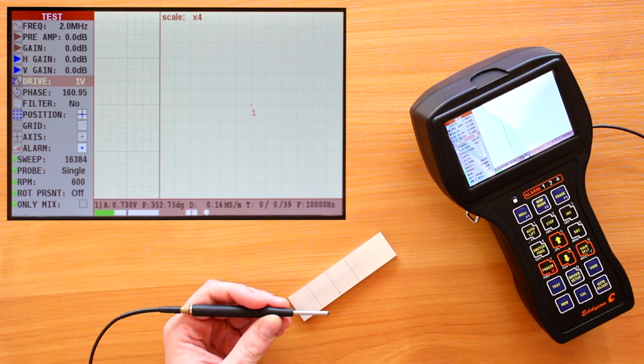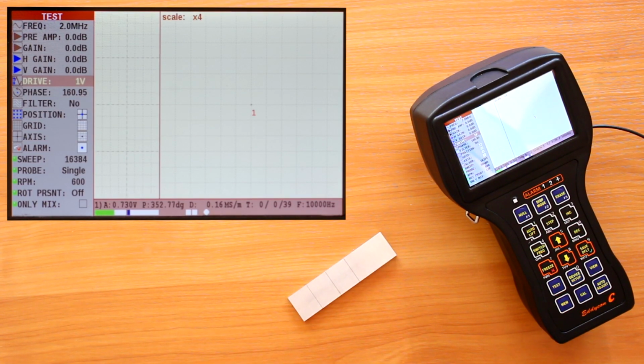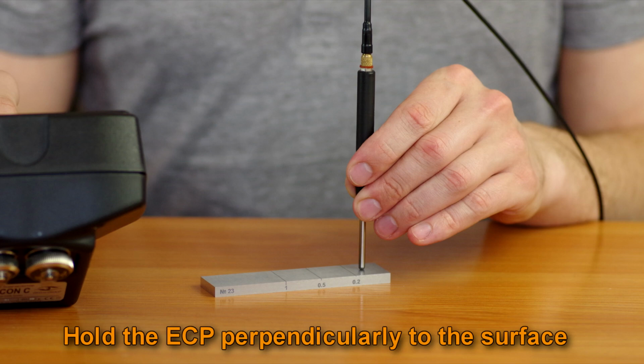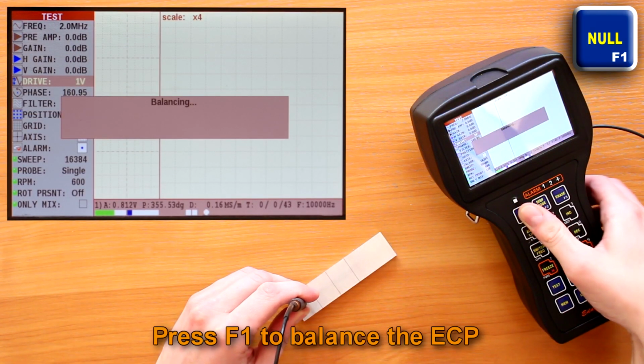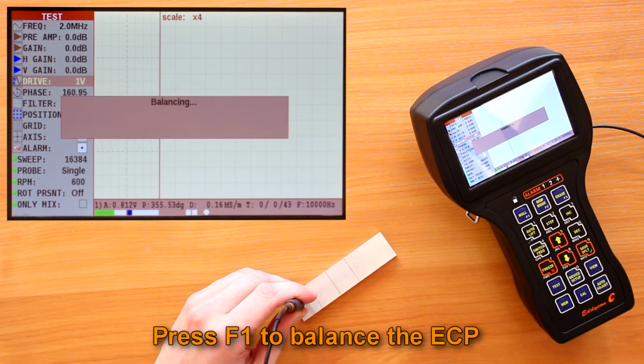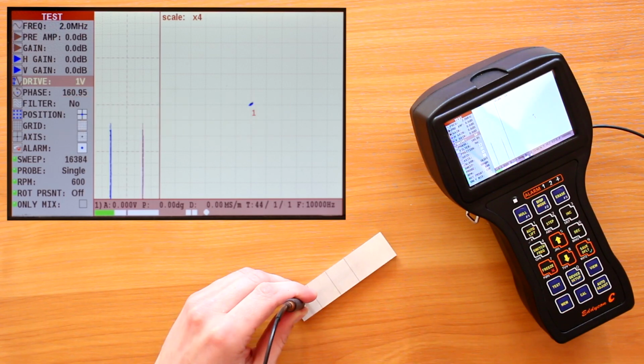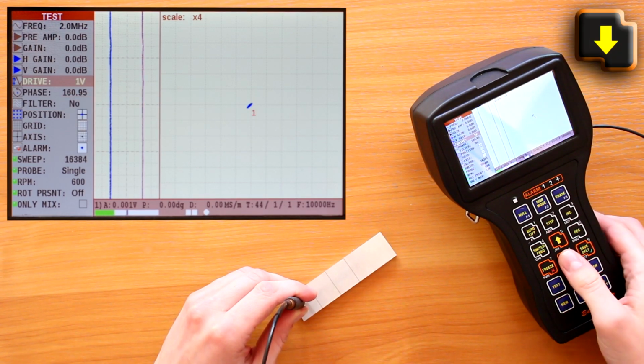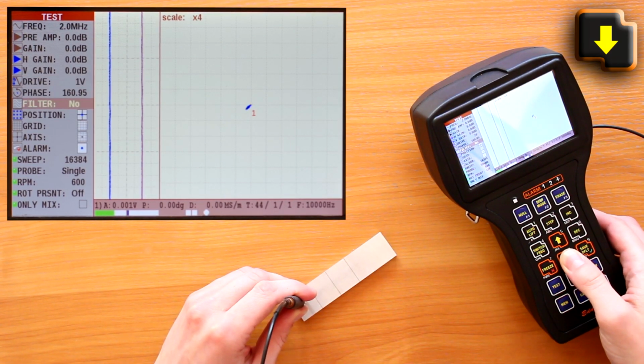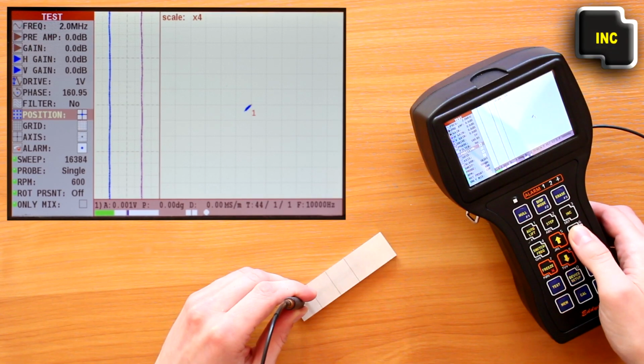Move the ECP to the flaw-free area of a calibration block. It is required to hold the ECP perpendicularly to the calibration block surface. Press the F1 key to balance the ECP. When working with aluminum alloys, it is recommended to position the center of the complex plane in the lower right corner.